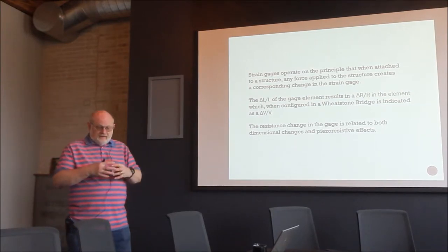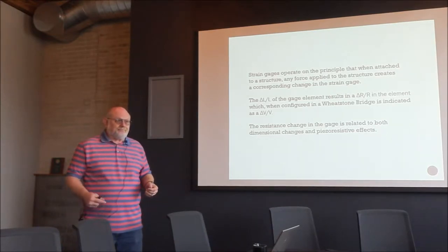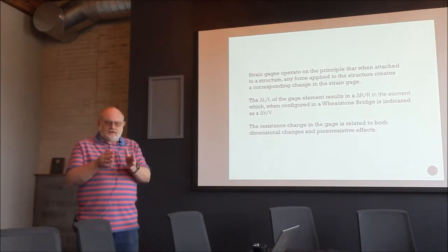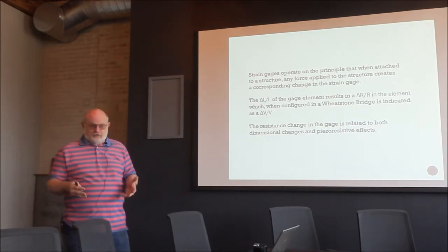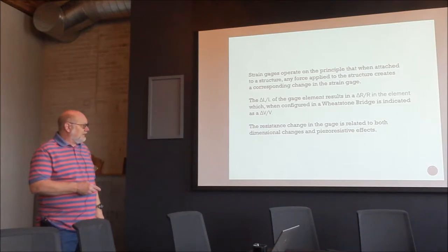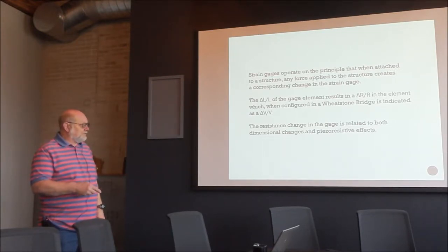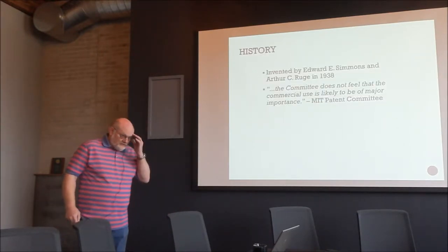Strain gauges operate on the principle that when attached to a device, any deformation in the device causes a corresponding deformation in the gauge, which produces a change in resistance. We're really measuring ΔL/L — change in length over length — as a change in resistance over resistance. In a Wheatstone bridge, that gives a voltage offset corresponding to strain.